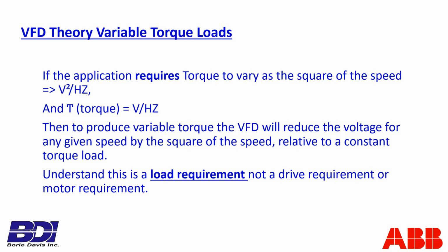Okay, now I have to admit that I will, in many cases, change that to standard linear volts per hertz, because linear volts per hertz gives me more breakaway torque down at the low end in case, on a pump, there's any particulate that settles in the impeller. That will cause a greater torque requirement at 0 speed than the pure centrifugal load with nothing inhibiting it. So that's just something that you might see that would manifest itself as a load that you try to start, and the load would just kind of sit there down near zero speed and draw a lot of current, mainly because it doesn't have enough voltage to break it free.